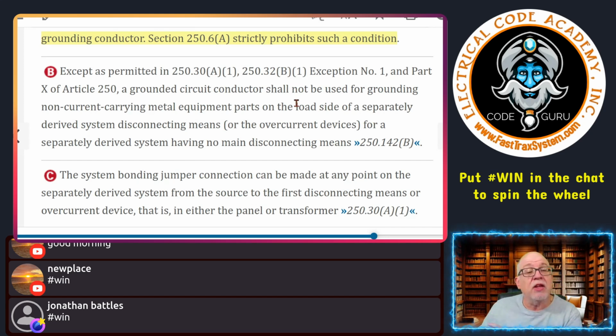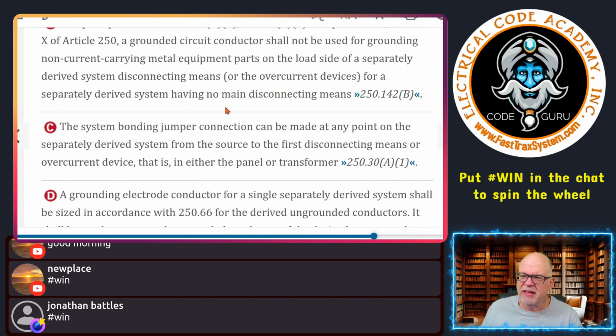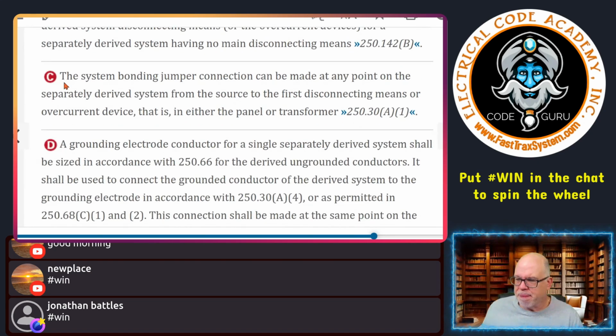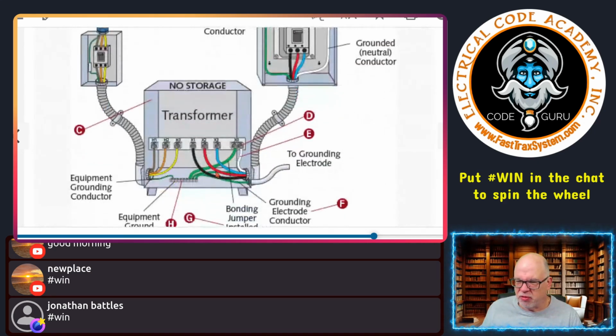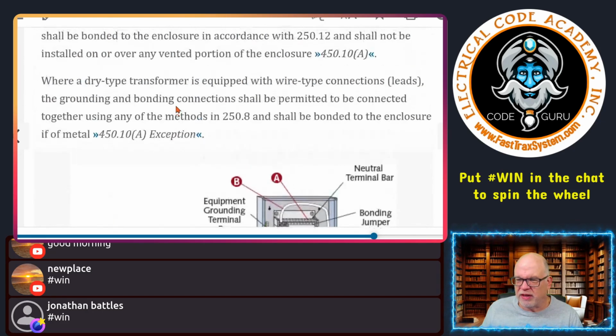All right, so accepting those accepted practices, the everyday rule for you and me is that I do not want that neutral connected to the enclosure. I need it to be floating in this case because we put the system bonding jumper down in the transformer. That's why we did it, okay? Now, C is referring to right here. So this is the transformer rule. And here's what it's saying.